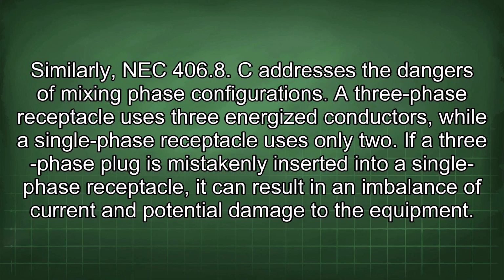Similarly, NEC 406.8(C) addresses the dangers of mixing phase configurations. A three-phase receptacle uses 3 energized conductors, while a single-phase receptacle uses only 2. If a three-phase plug is mistakenly inserted into a single-phase receptacle, it can result in an imbalance of current and potential damage to the equipment.